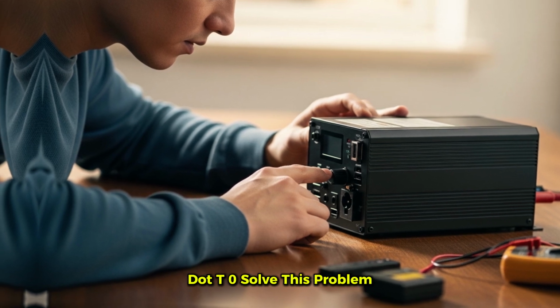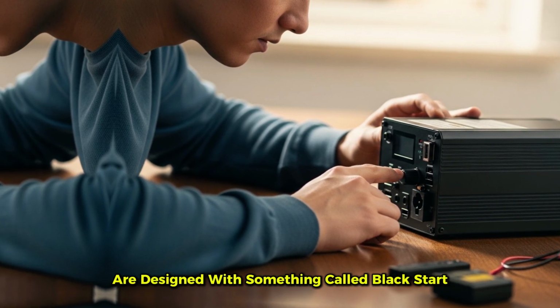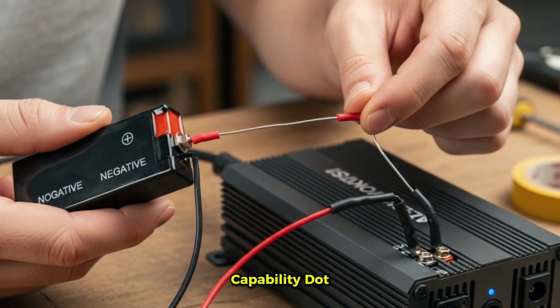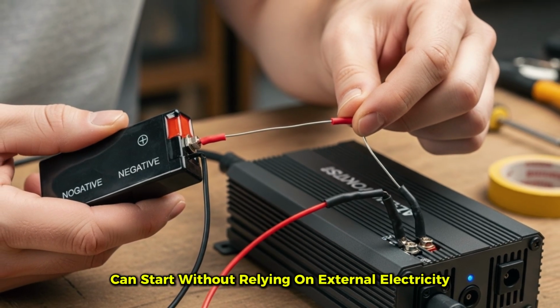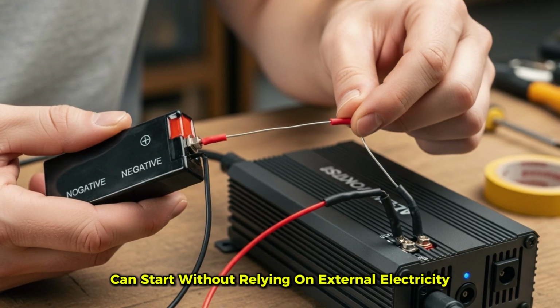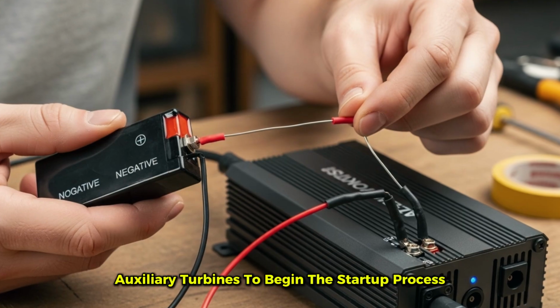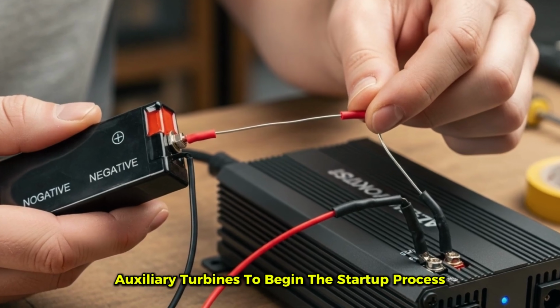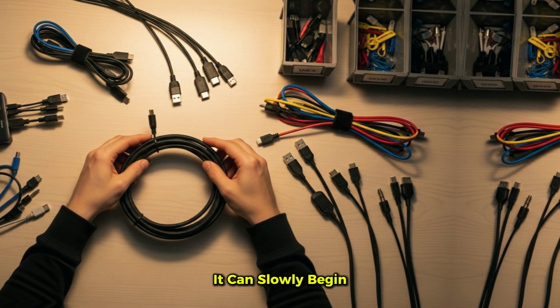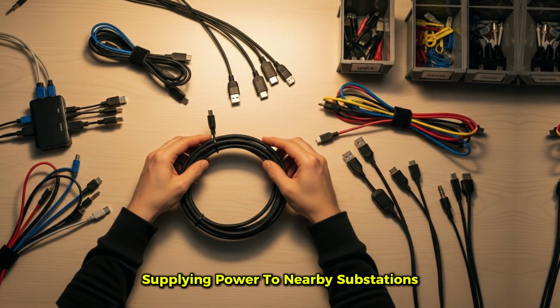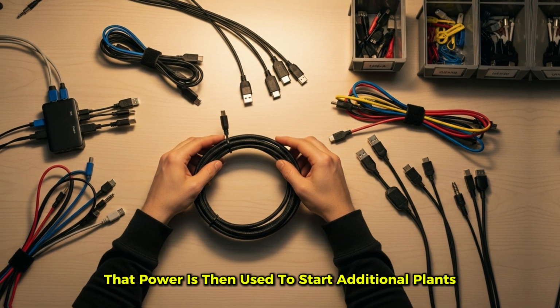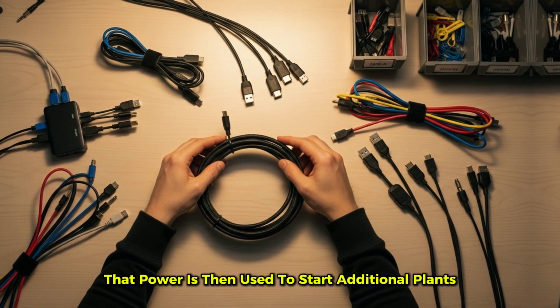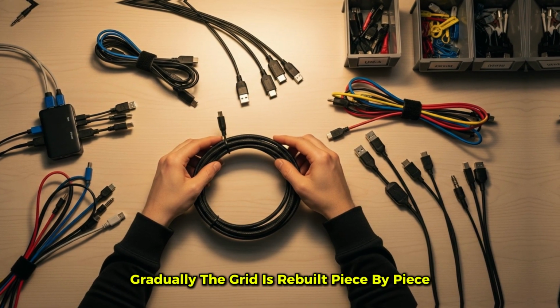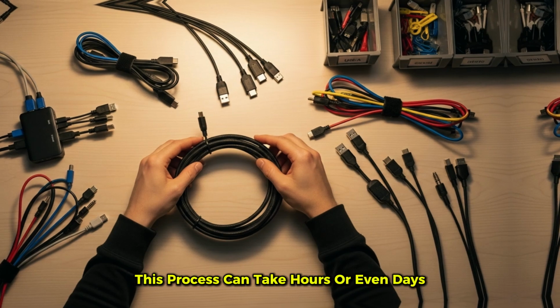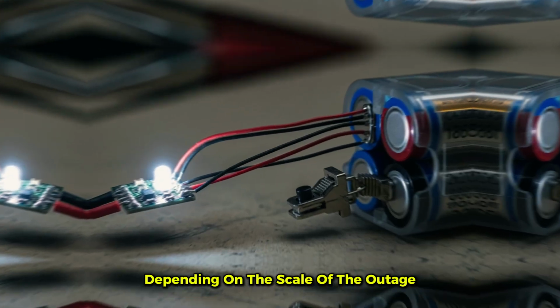To solve this problem, certain facilities are designed with something called black start capability. A black start power plant can start without relying on external electricity. These plants may use diesel generators, batteries, or small auxiliary turbines to begin the startup process. Once one plant is running, it can slowly begin supplying power to nearby substations. That power is then used to start additional plants. Gradually, the grid is rebuilt piece by piece. This process can take hours or even days depending on the scale of the outage.